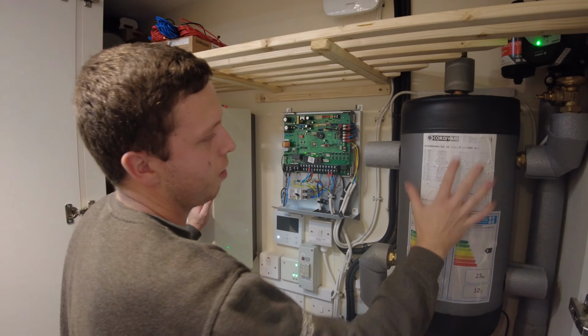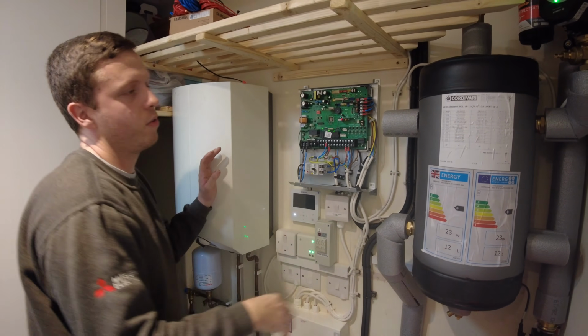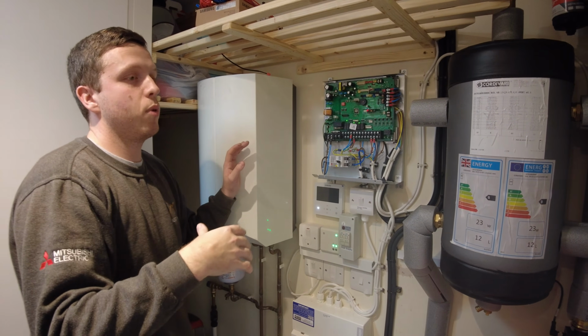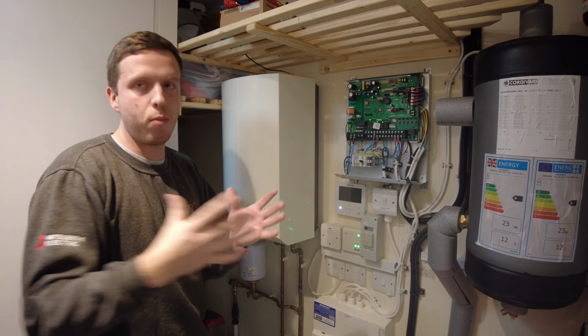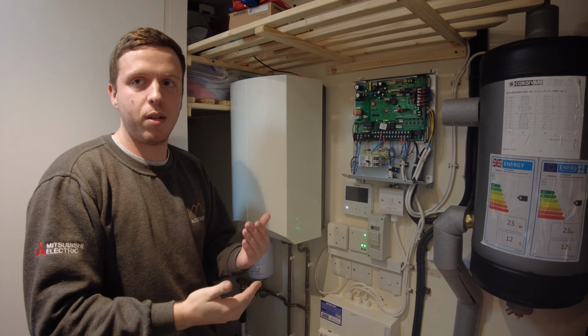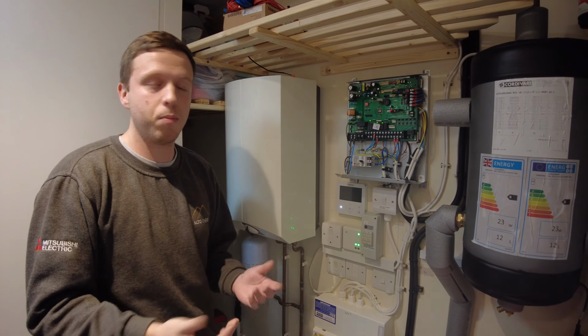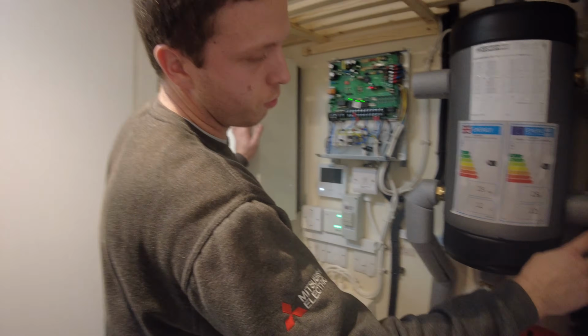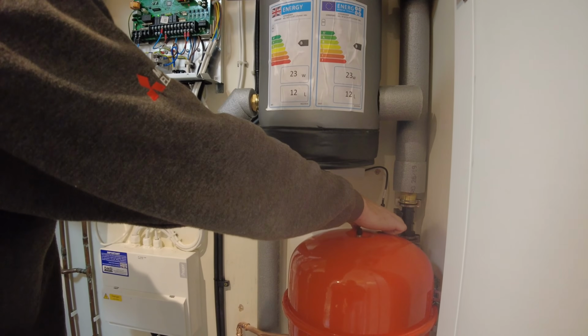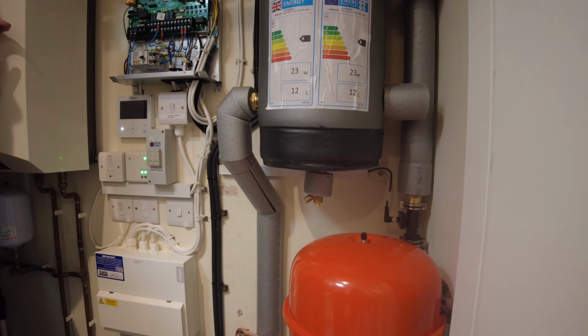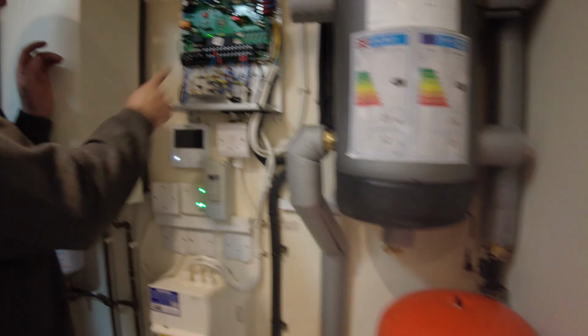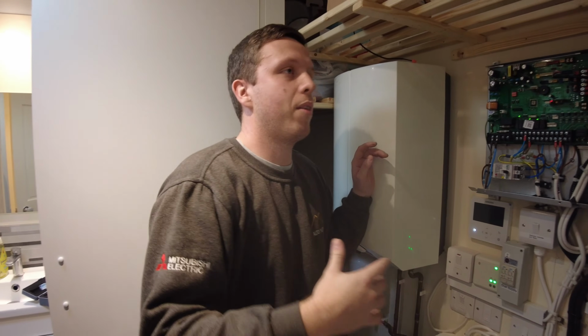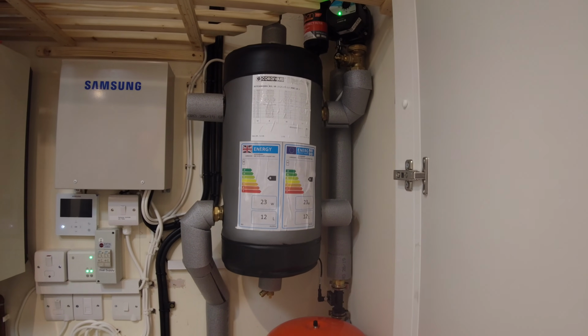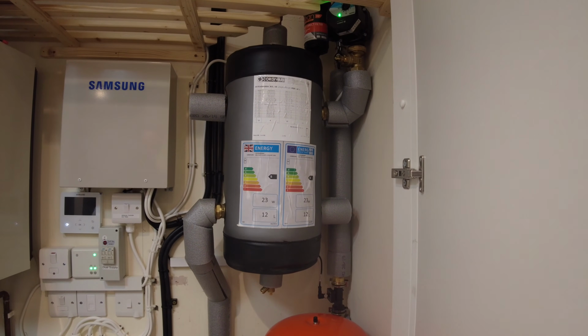And then further down, you've got your buffer for your system. The buffer is there for when it does the defrost, just that volume of water, so it can actually do the defrost properly via the schematic from Samsung. And then further down, you've got your flow switch, flow sensor, which basically relays back to this brain unit up here about the flow rate. So for Samsung, ideally, we want about 3 times the size of the unit.